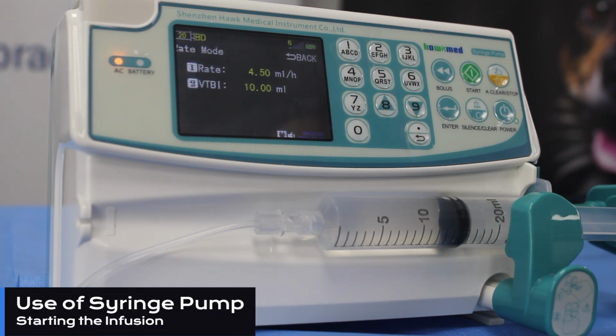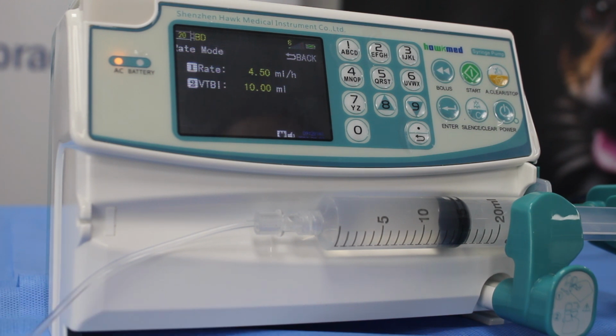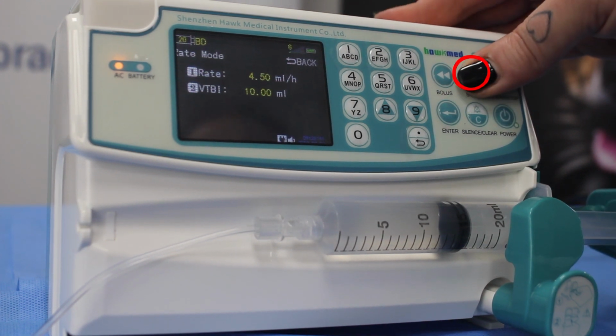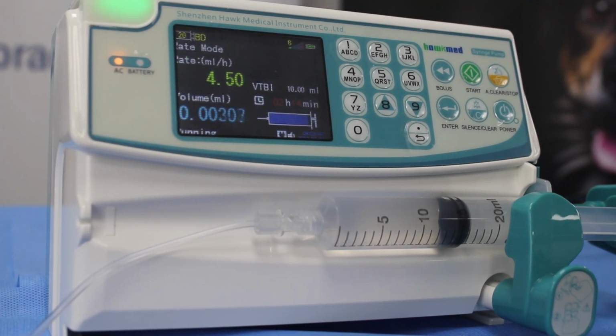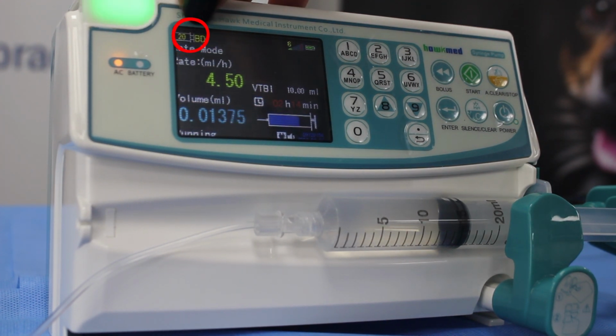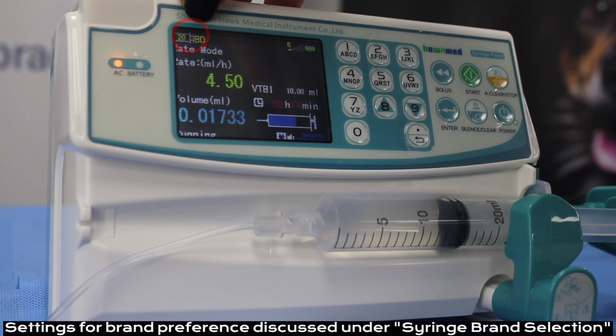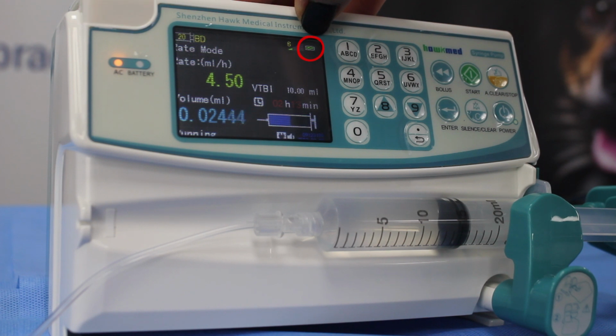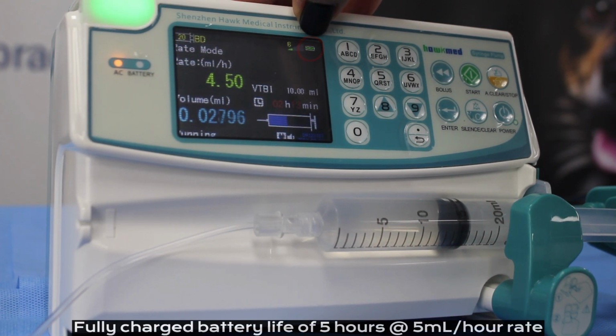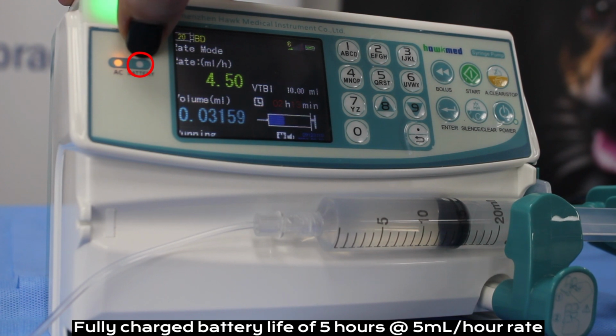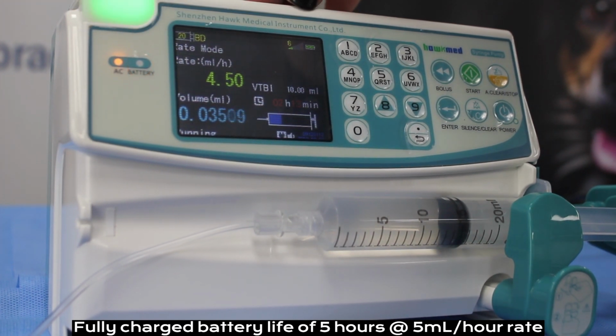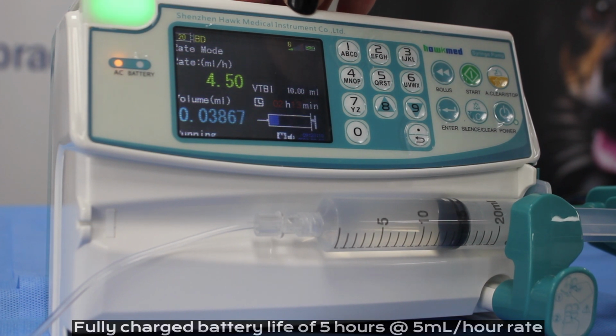Once you've connected your infusion to your patient and clamps have been released and you're ready to start your infusion, we can press the start button. This will start infusing your syringe to your patient. In the screen, we can see at the top our 20ml Luer Lock BD syringe has automatically updated due to our calibration. We have here our battery charging, which is showing a full battery charge, which we can also see as our battery light is no longer illuminated, which means this pump would be ready to take off power supply if needed.